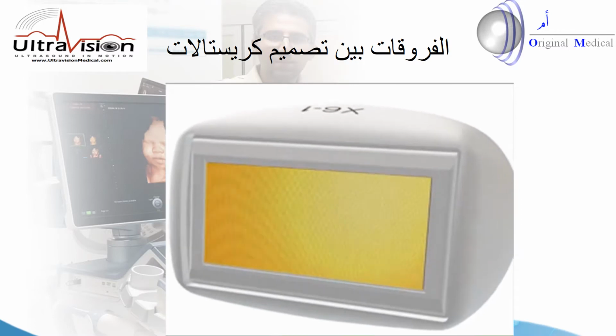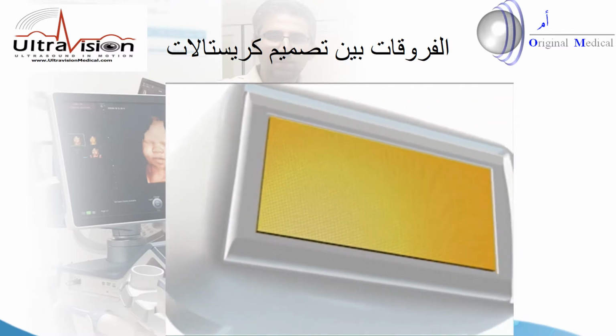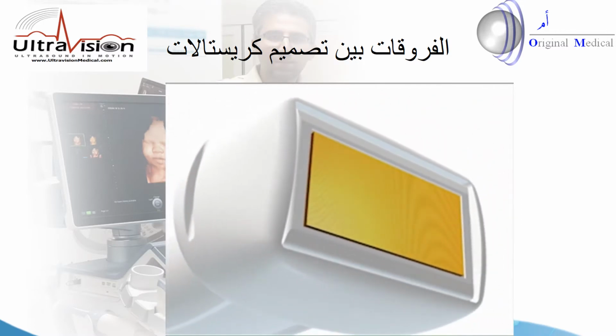It has over 9,000 elements. The exact number is 9,212. I often get asked why we need so many. We need all of these elements for the three-dimensional acoustic beam forming that allows the X6-1 to steer and focus throughout the entire field of view. Let's first look at why.